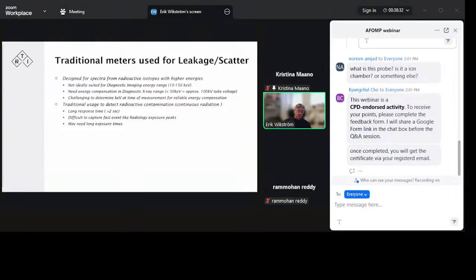So then long exposure times may be needed for it to do some sort of work, but then for that you need to turn down the mA, the tube current, so that you reduce the workload on the X-ray machine. But that produces a weak output, a low dose rate, and that puts an extra challenge onto the instrument for sensitivity. And we know that that's also another challenging area for traditional meters.